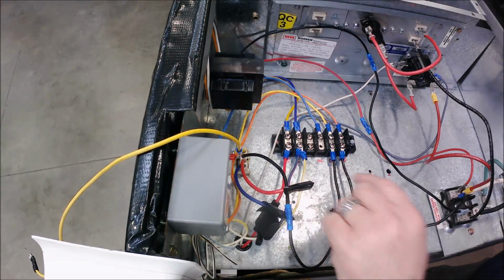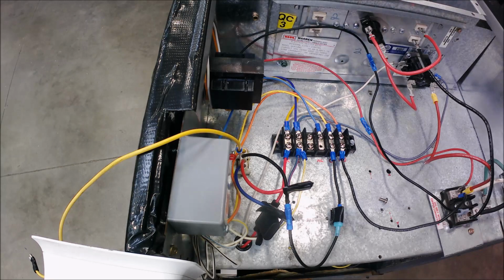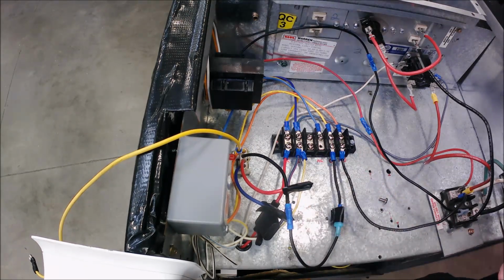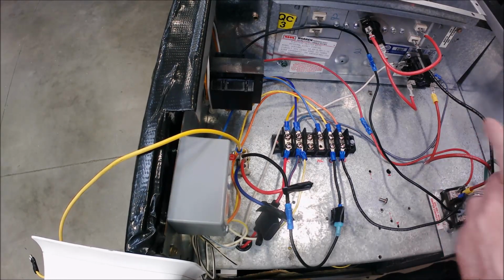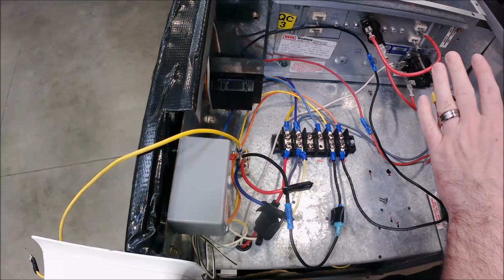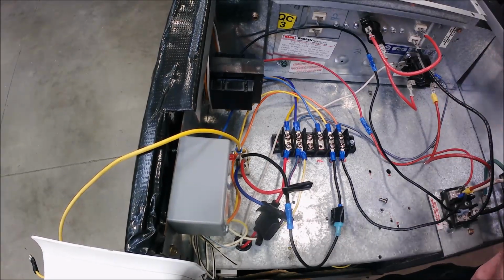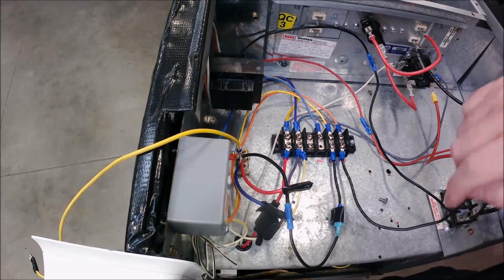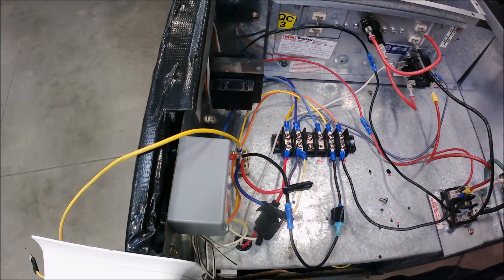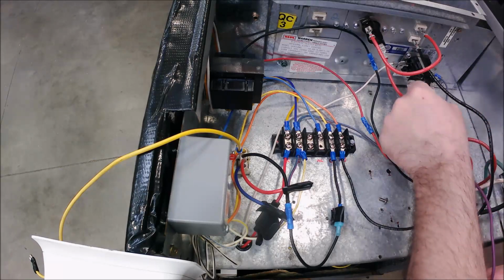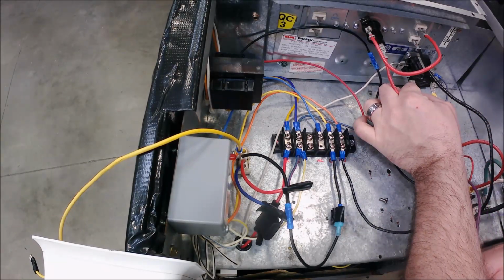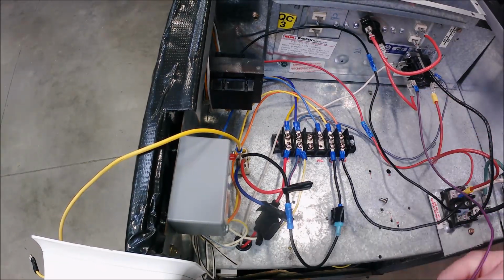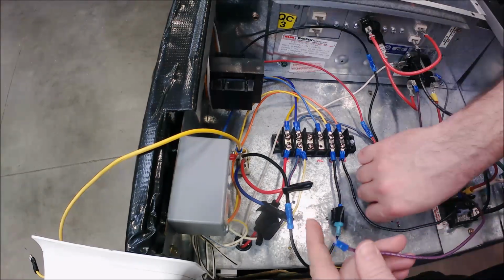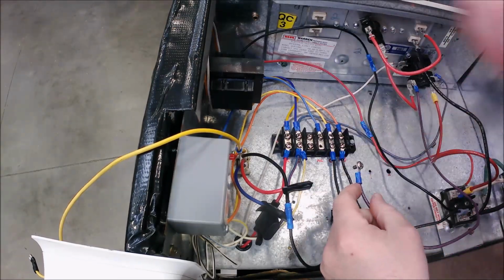This is easy. Alright? The normally closed connection we're going to use in this setup as a redundant safety for heating mode. Now we've only got our electric heat up here. Like I said, treat this as a conventional setup. What we're going to do here on this normally closed is tie in our heat strip with the fan. I don't need a call on G for the fan to work in heat mode.